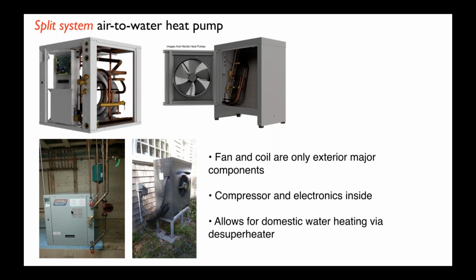And I like that for a couple of reasons. One is it brings most of the electronics and the electrical components inside the building. So they're going to have less exposure to the elements, obviously inside a building versus outside through a Canadian winter. The other thing that does represent an option with this particular configuration is you can order this with a domestic water desuperheater, which means you can do at least some domestic water preheating with this unit, because again, none of the water has to go outside. So that's an example of a split system.